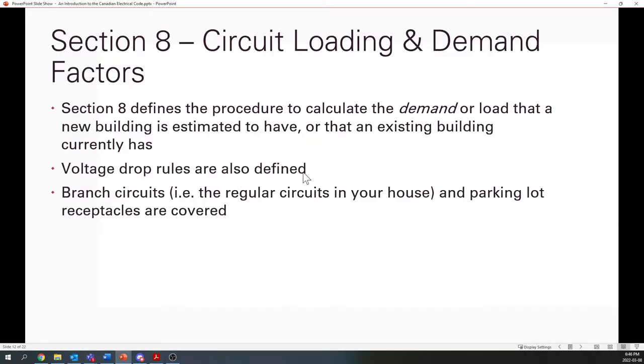Voltage drop is the other important thing that's defined here in section 8. Generally, the code defines a maximum of 3% voltage drop between a panel board or a load center electrical panel. Those terms are all synonymous, essentially. So 3% between the panel board and the load or the receptacle, or 5% between the service entrance, like we were talking about in the last section, and the receptacle.